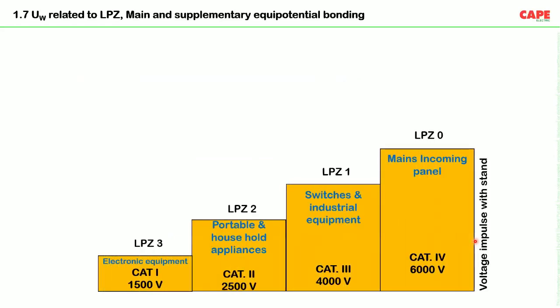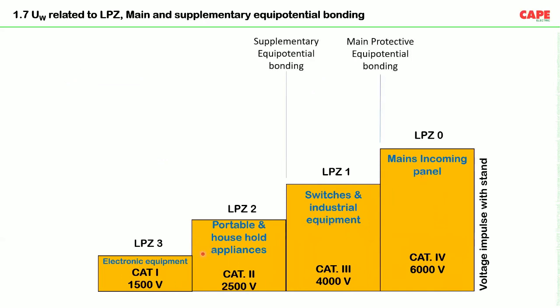Now, what is this impulse voltage? There are 4 categories. You can see here: category 4, category 3, 2 and 1: mains incoming panel, switches and industrial equipment, portable equipment and electronic equipment. If we look at the electrical engineering safety standards, as I said, the base for everything is equipotential bonding. Between the mains incoming and the switches or the fixed part of the installation, with respect to lightning protection, the building is classified into LPZ, lightning protection zone 0, zone 1, zone.